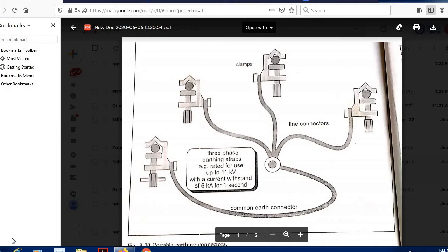If in certain places you have a permanent earthing connection through a switch, whenever you want to connect the system to the earth, you can put the switch on and then it gets connected to the ground. And if you are working where the permanent arrangement is not there, on a certain section of the circuit, then you may have to use, for extra safety, a local earthing strap.